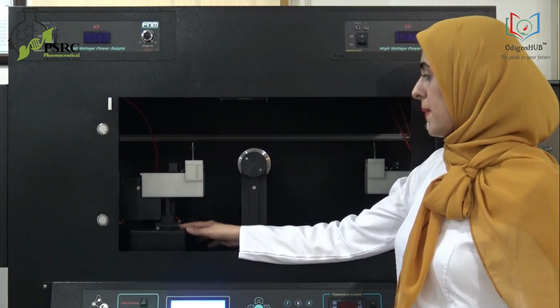The high voltage power supply can provide the risk of electric shock. Before starting to work with high voltage, all safety measures should be considered. All connections, especially the earth, should be investigated. Make sure they are connected. You shouldn't open the door of the machine while the high voltage is working. Also, you shouldn't connect the crocodile cable of high voltage to any place except the tube.